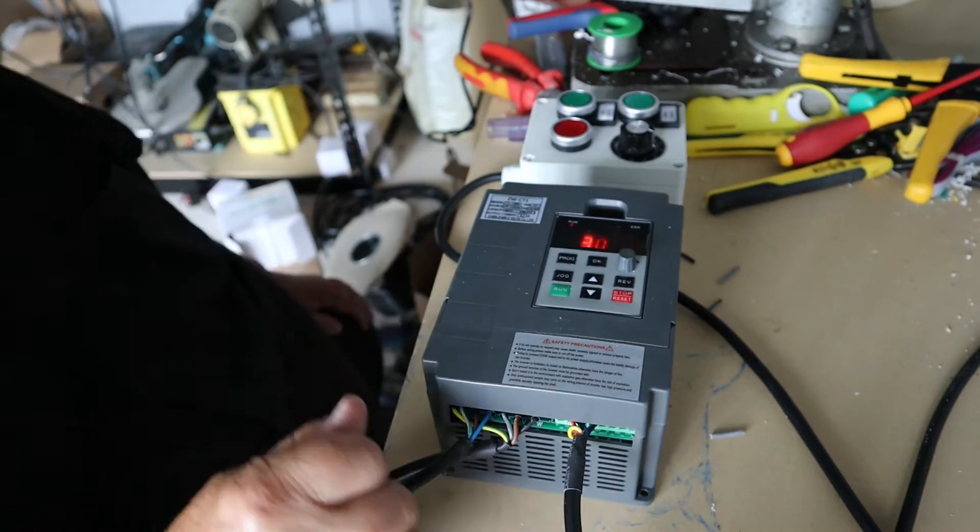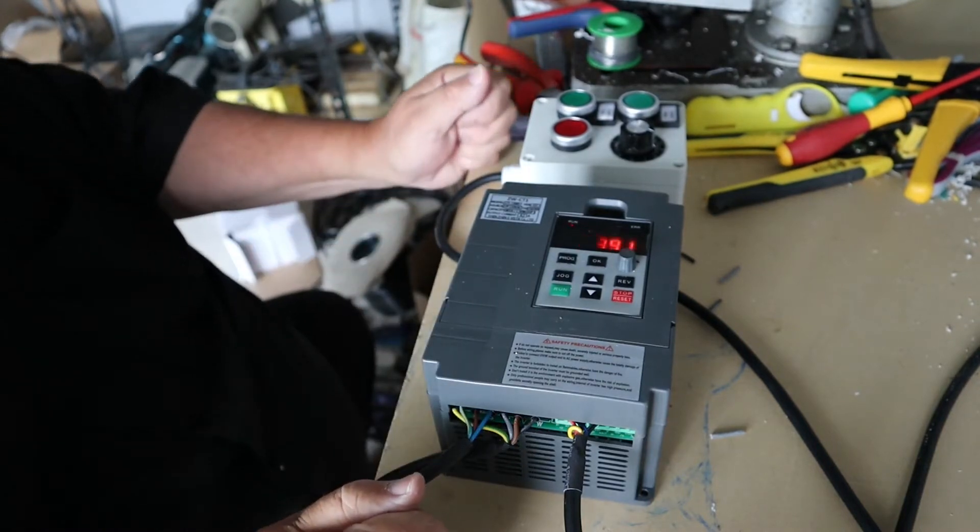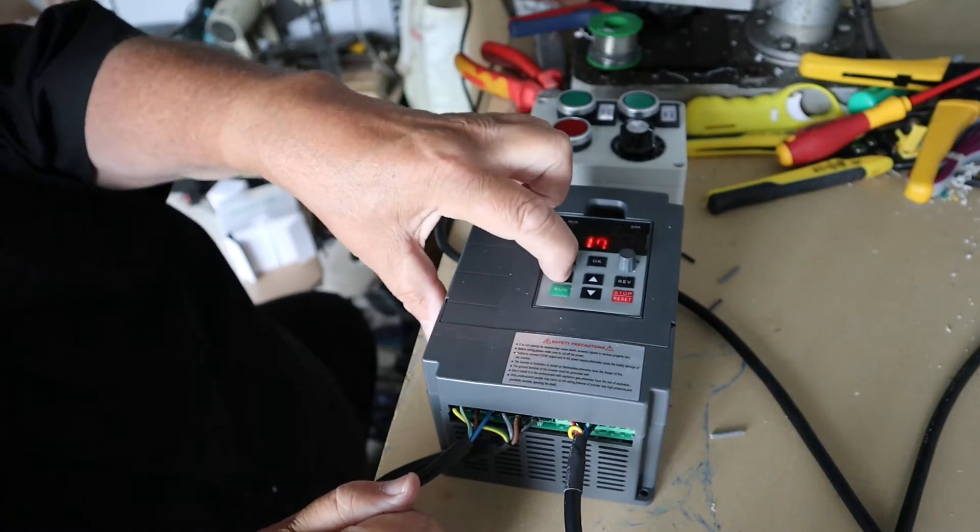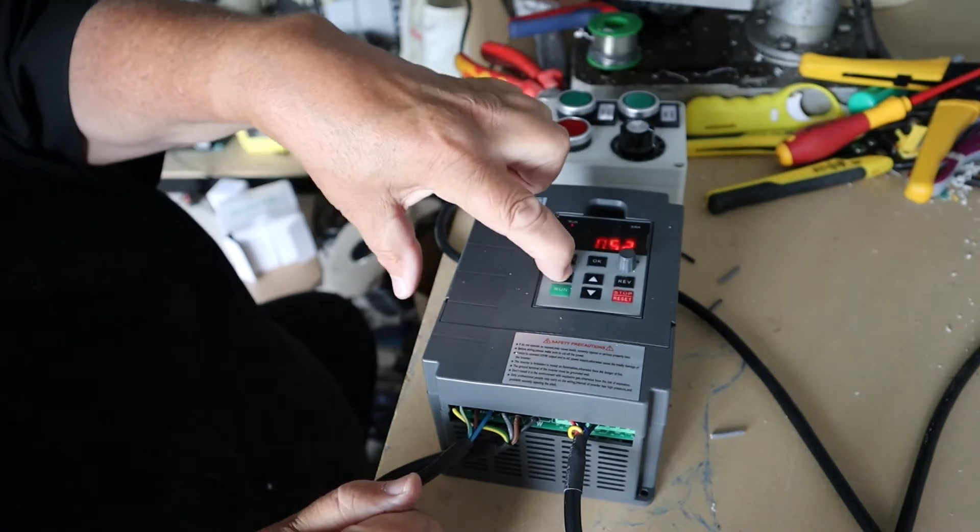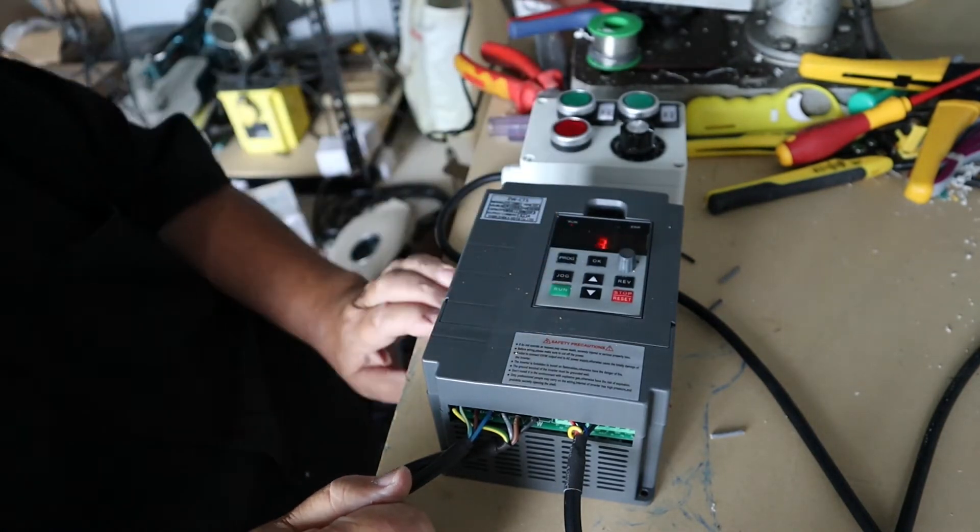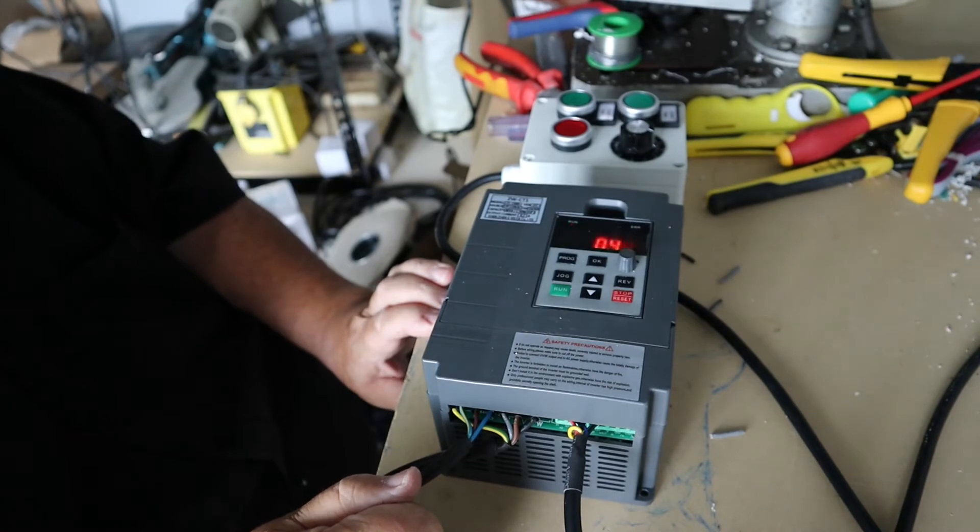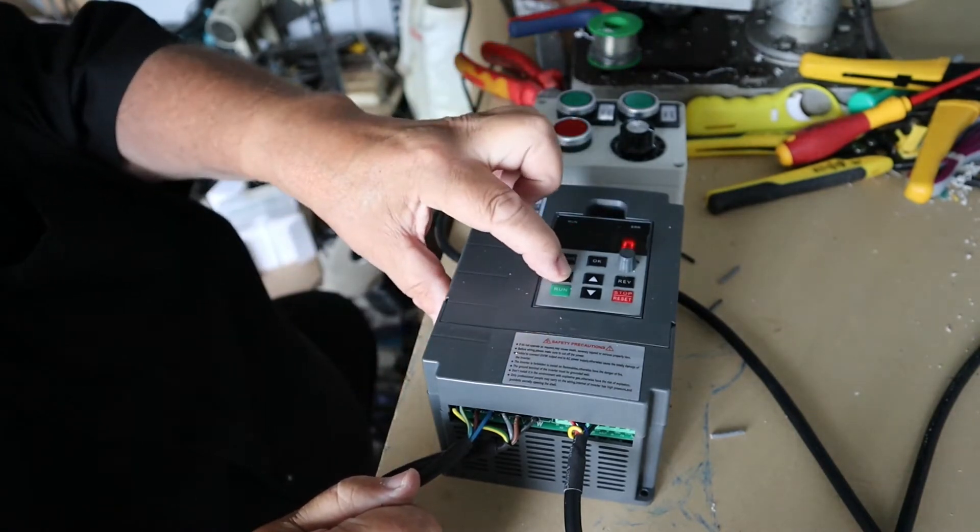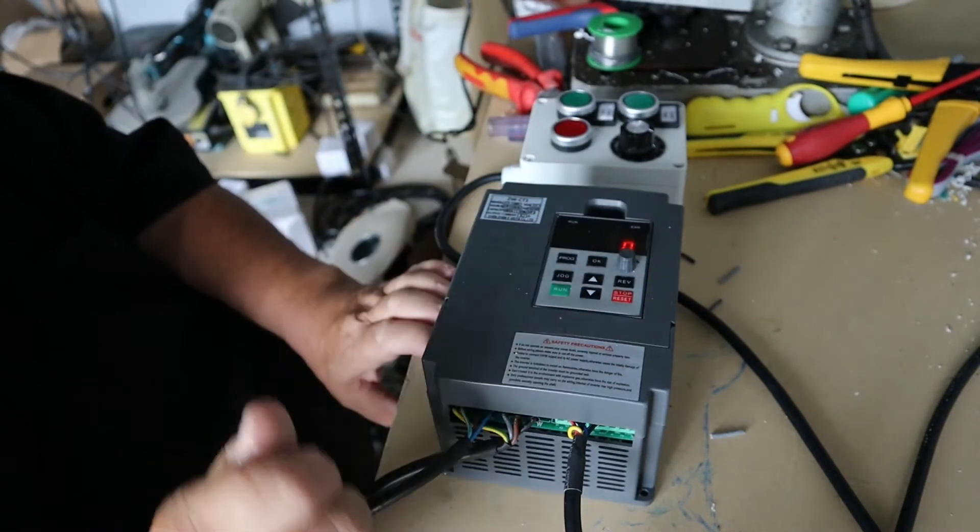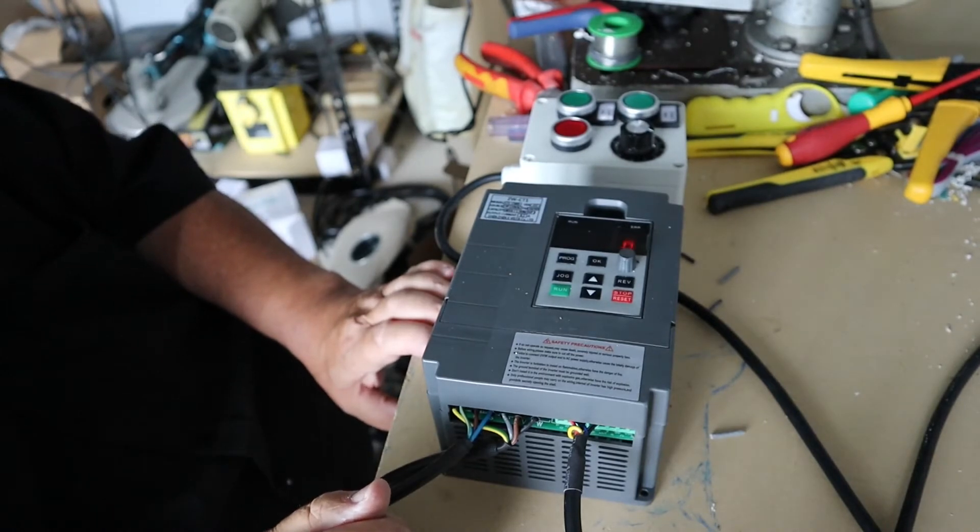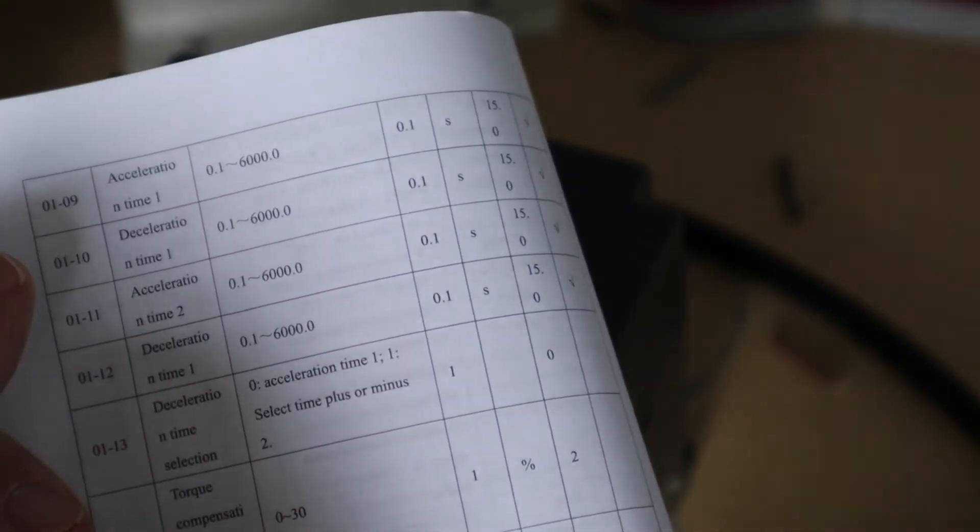There is something else about these inverters. There is no jog facility. The jog does not work on them. I will wait for it to stop and you will see. No jog. It is on the board but it does not work.